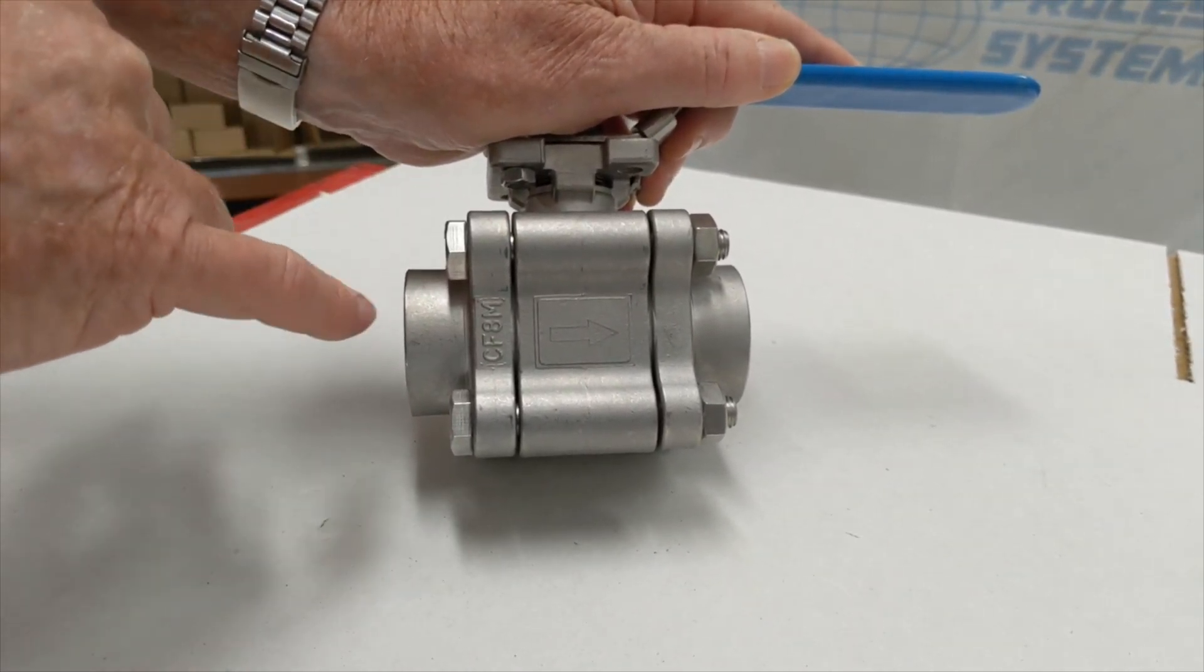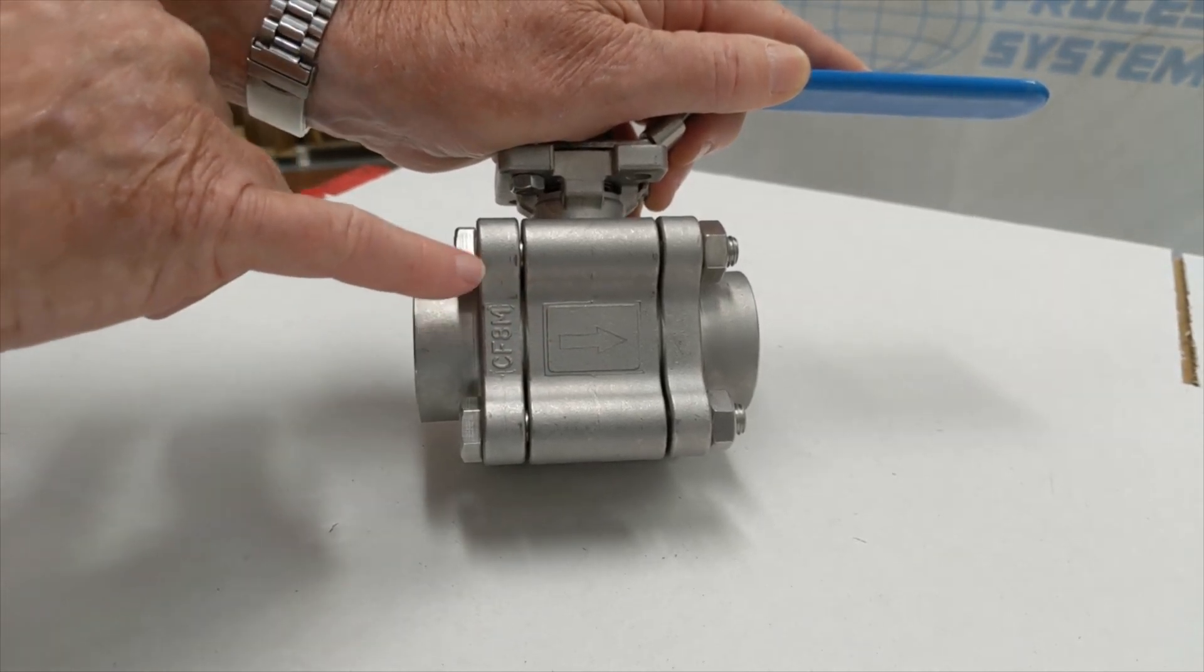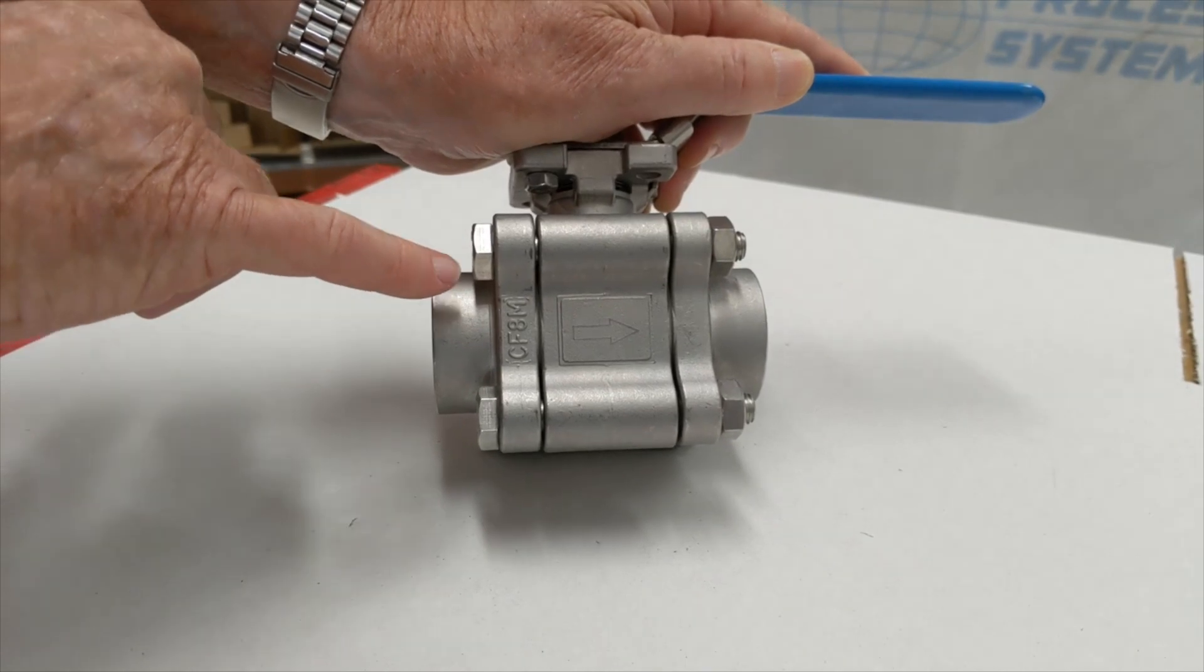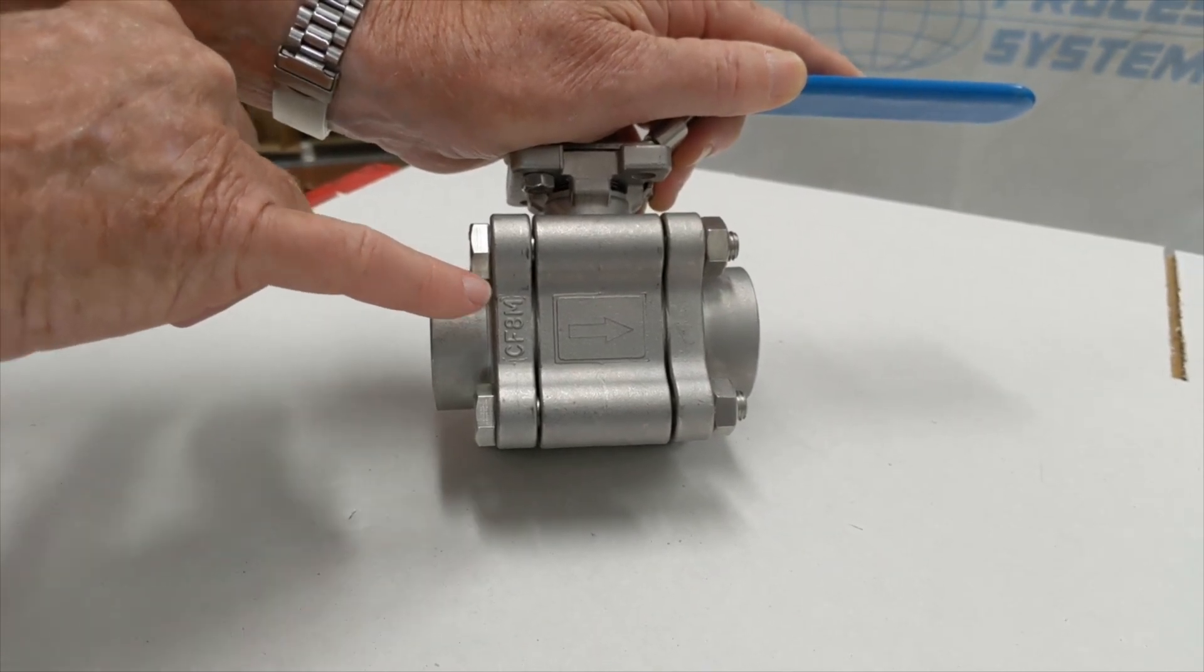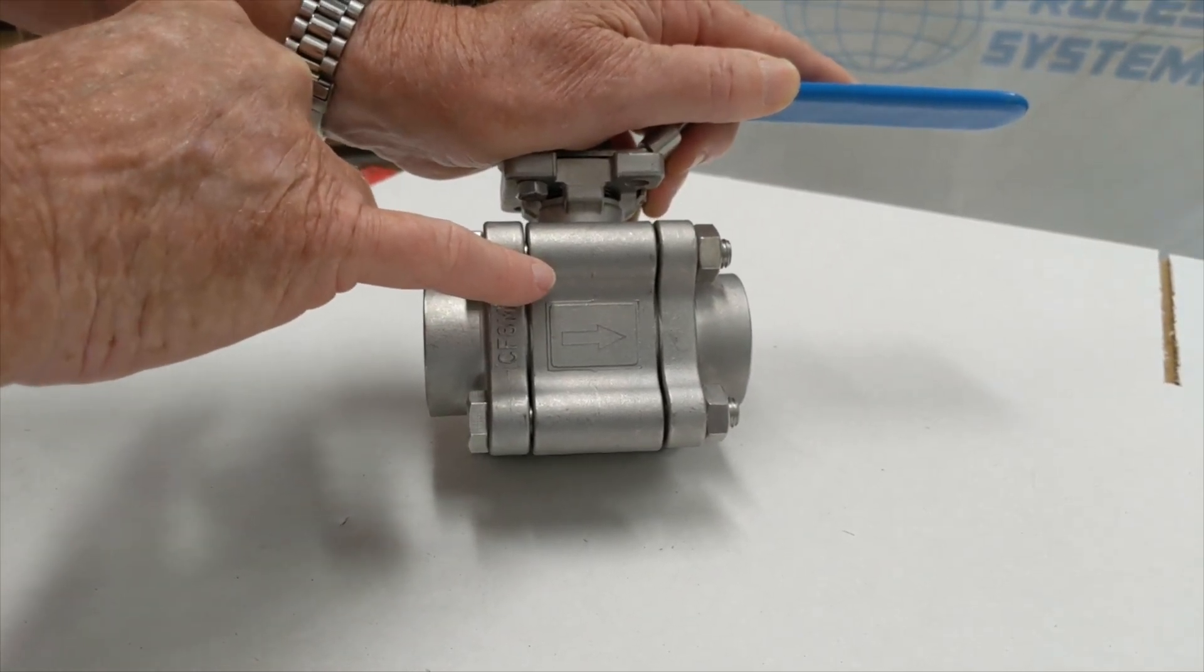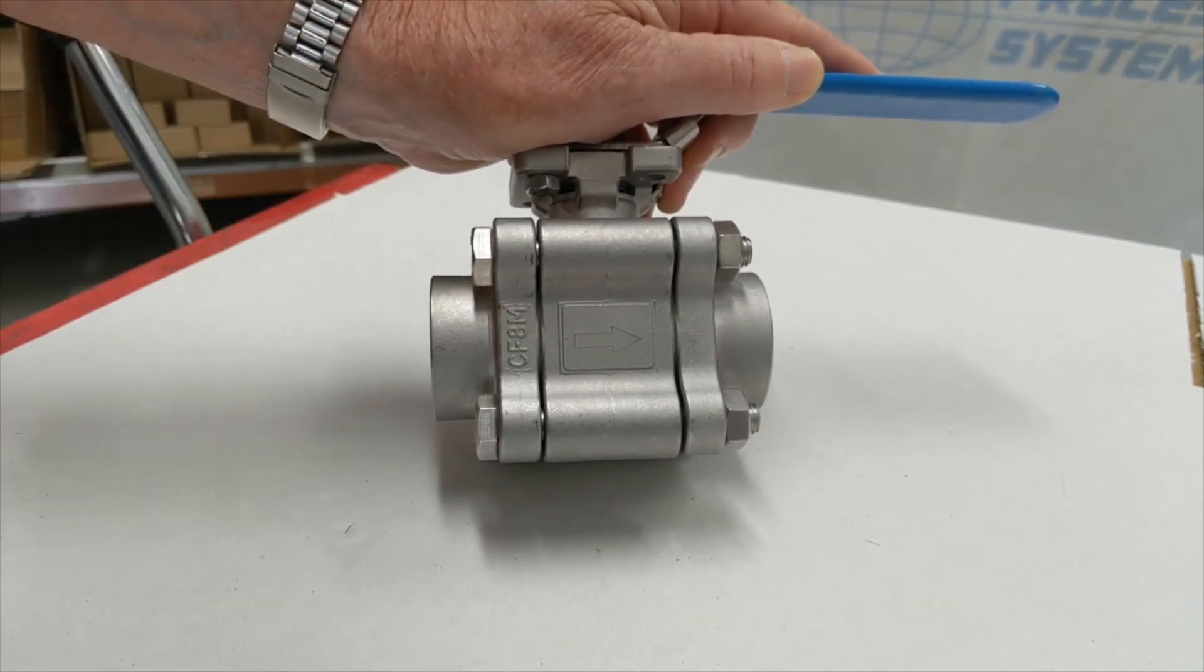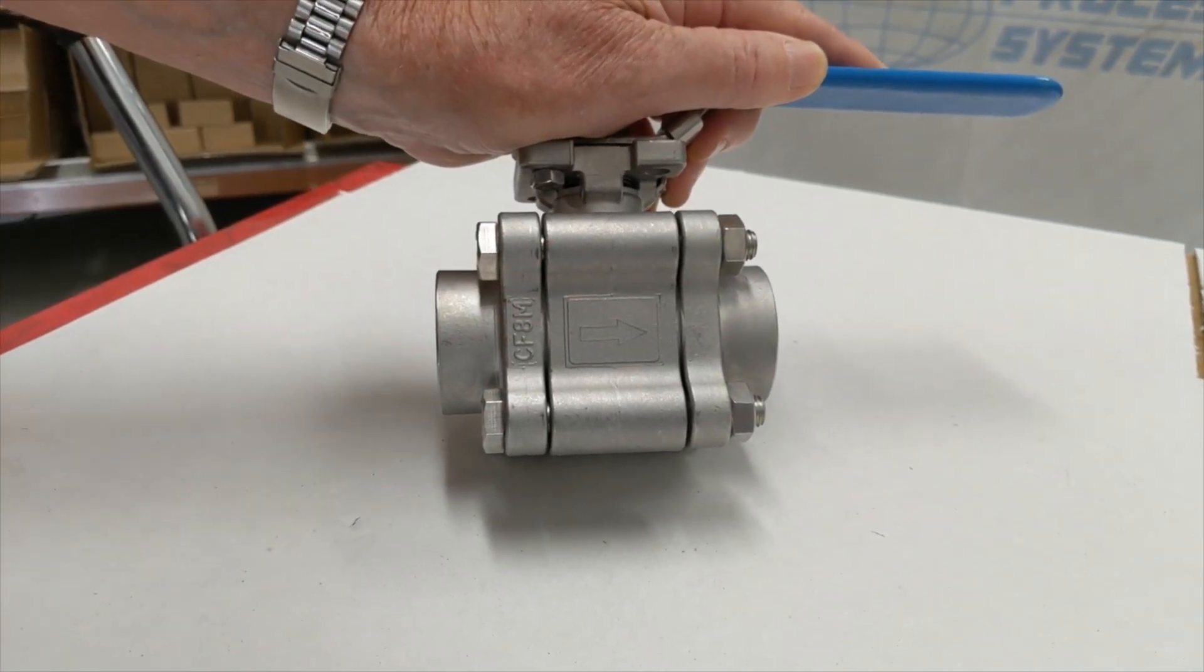The unidirectional device here—when the valve is closed, the metal ball has a bleed hole into the cavity so that the pressure is equalized in the cavity to get back pressure upon the metal seat.